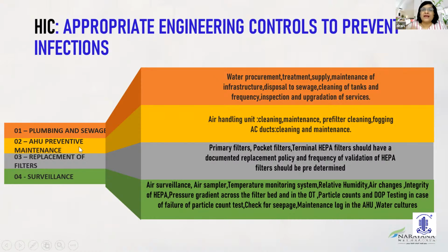AHU preventive maintenance, again, is an area limited to a certain number of people. For the air handling unit, the cleaning, maintenance, pre-filter cleaning, fogging, and AC duct cleaning and maintenance are very, very crucial. Whatever filters are present, HEPA filters, primary filters or pocket filters, should have a documented replacement policy, and the frequency of validation of HEPA filters should be predetermined.